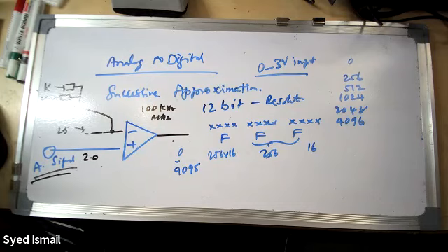Practically, you will not use that much in most real-time applications. In real-time applications, even if you sample so many times, you will average it to a few samples per second. But certain events require you to measure the voltage very accurately for a long time. For example, energy measurement. If you want to go for energy measurement, we are talking about 50 hertz, so you have to measure very accurately in digital. When you really go for accurate digital 3-phase meters, they measure quite fast. But again, coming to the line, 12 bit is enough.